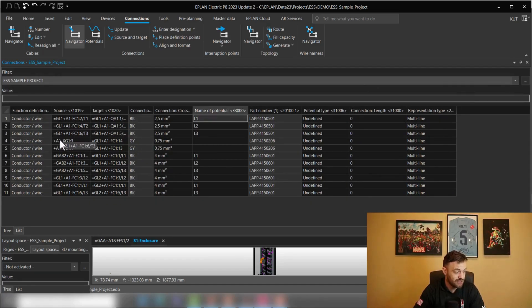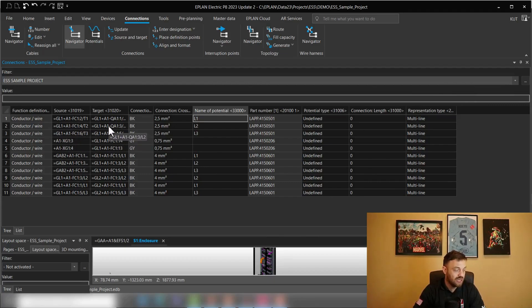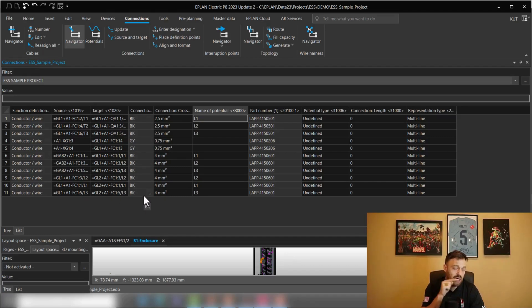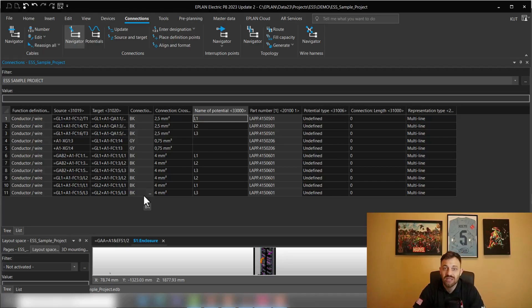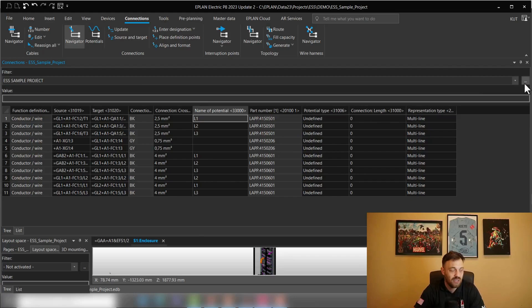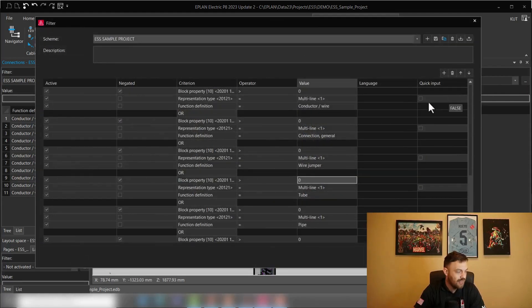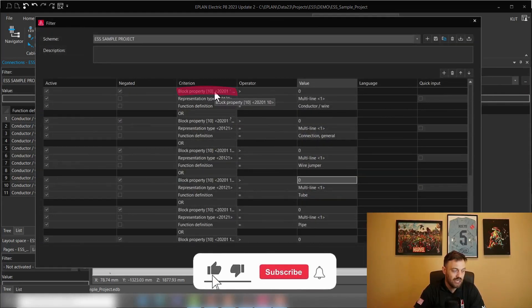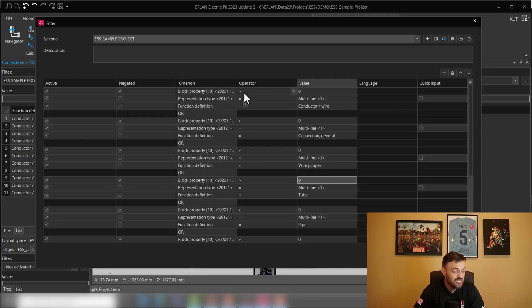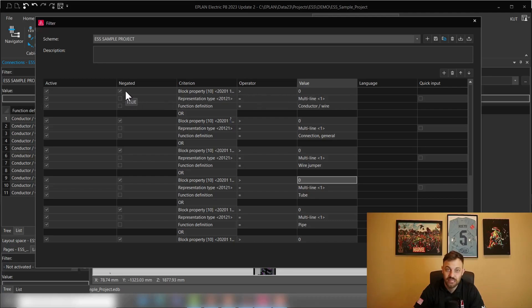So in this case, ePlan tells me there are some wires which are not routed yet. So how this looks like and how to utilize it, I'll show you shortly. But what does this filter contain now? So if we click here on the three-dot button, we see it's called block property 10. I'll go shortly into the block property so you know exactly what to do with it. And here we see it's called block property 10 and here we see the operator is bigger than 0 and negated.